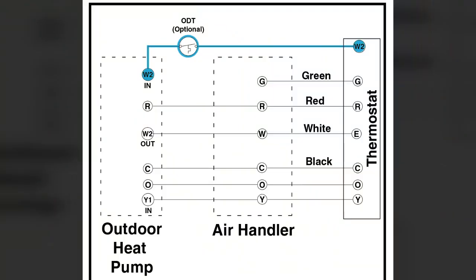W2 and auxiliary is essentially the same thing. But on this diagram, we're showing it going outside to an optional thermostat. All HUD manufactured housing requires that we incorporate and send out with the unit an outdoor thermostat, which will hold off the electric heat unless it's below, I believe it's 45 degrees, don't quote me on that. But that's essentially what it does.